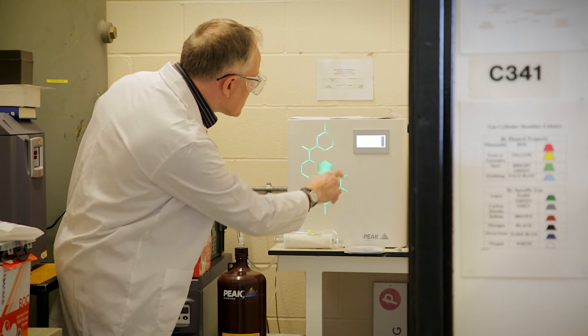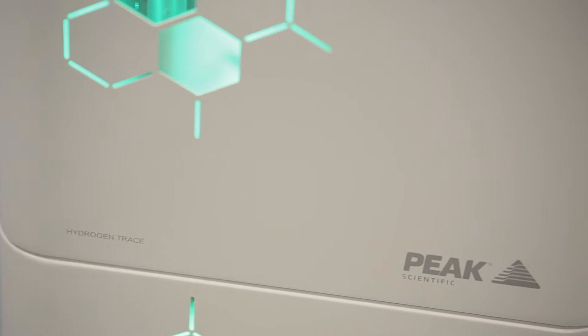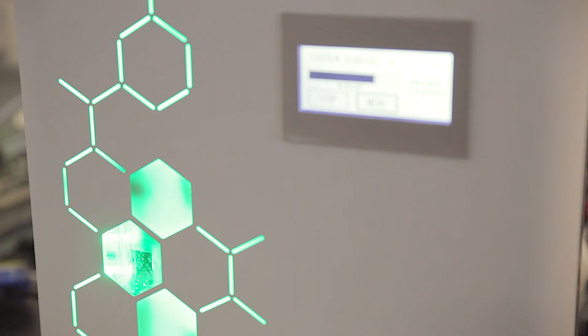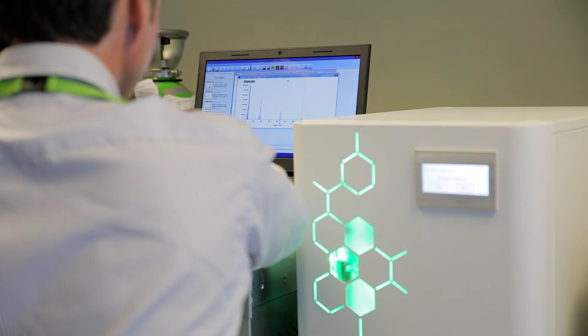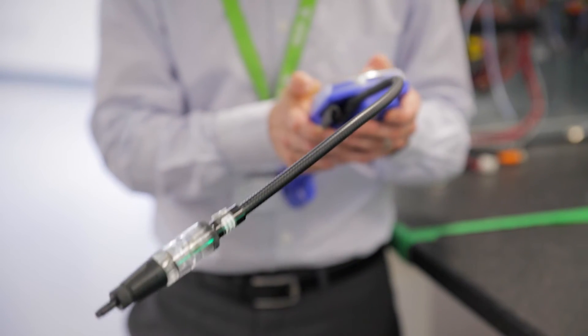The Hydrogen Generator is the safest way to have a supply of hydrogen within the lab. The Peaks Precision Hydrogen Generator range offers customers safe production of hydrogen with a number of safety features built into all of our units. We have over-pressure and under-pressure sensors, forced air ventilation to prevent any mixture of oxygen and hydrogen from forming within the unit if there was an internal leak, and we also have a leak detection system which operates external to the system.